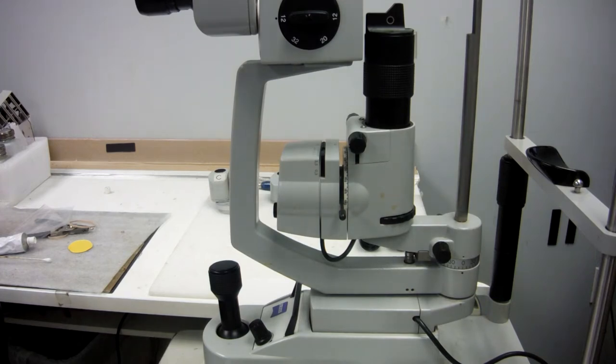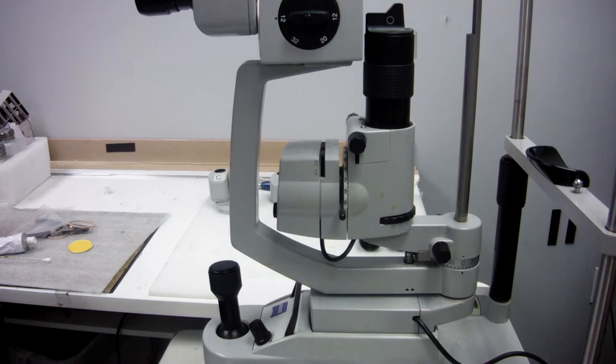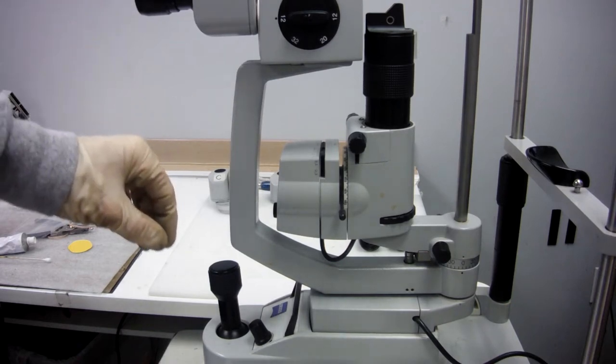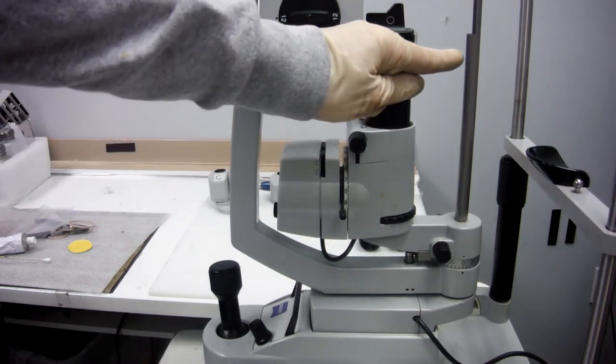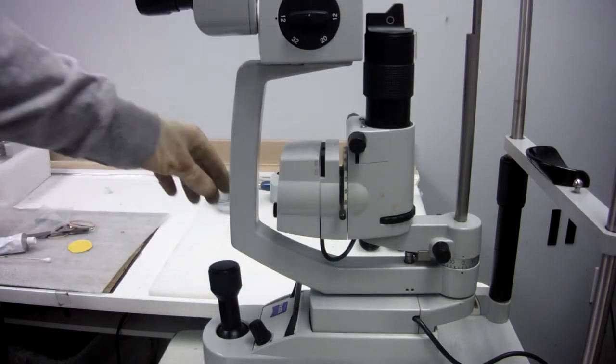On the SL120, if you were aligning the head, if I were doing it, first of all I would look through the viewfinder. I would look through the binoculars and make sure that I have equal space on each side of the bar.